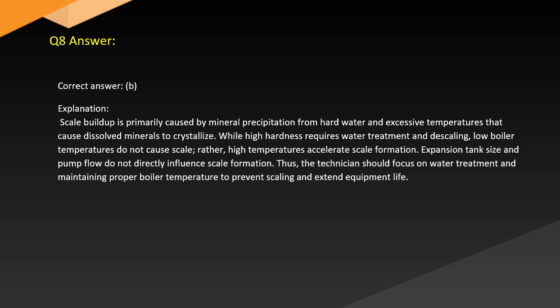Answer. Correct answer, B. Explanation. Scale buildup is primarily caused by mineral precipitation from hard water and excessive temperatures that cause dissolved minerals to crystallize. While high hardness requires water treatment and descaling, low boiler temperatures do not cause scale. Rather, high temperatures accelerate scale formation. Expansion tank size and pump flow do not directly influence scale formation. Thus, the technician should focus on treatment and maintaining proper boiler temperature to prevent scaling and extend equipment life.